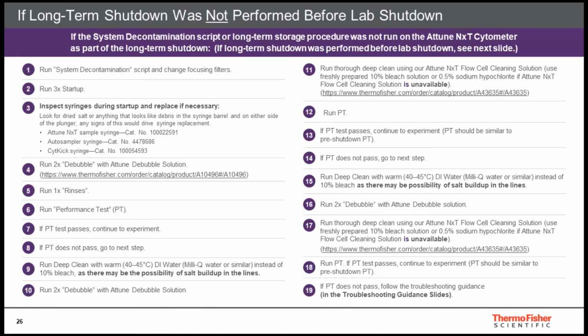If it doesn't, repeat the steps starting with running deep clean with warm water, going through the debubble, and running deep clean again with flow cell cleaning solution. Alternating between running the deep clean script with warm distilled water and flow cell cleaning solution will gradually remove salt and debris from the lines. If the performance test still doesn't pass following the above steps, please look through the troubleshooting guide for guidance. If that doesn't help, please contact Thermo Fisher Scientific Support with the serial number of the instrument to open up a service call.